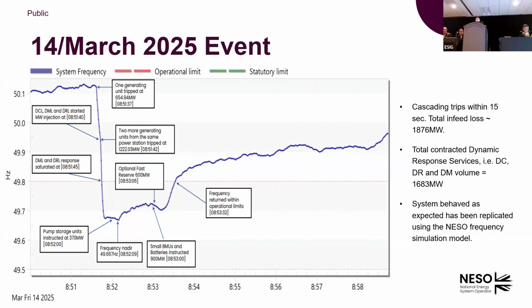We now have what we call very fast frequency response. People have to respond to the frequency change within 500 milliseconds. They need to fully deliver that response within a second if they see the frequency drop. That's mainly done by batteries, so we have a huge amount of very fast frequency response. It means that the frequency drop for a similar generation loss, compared to 2019, which led to the blackout, is this time just a really small frequency drop.